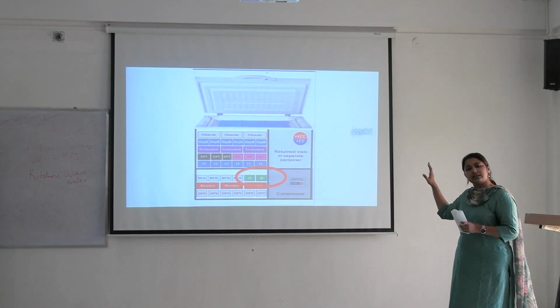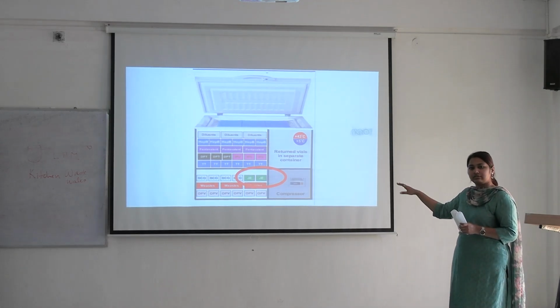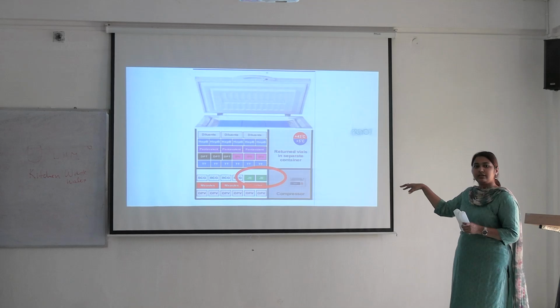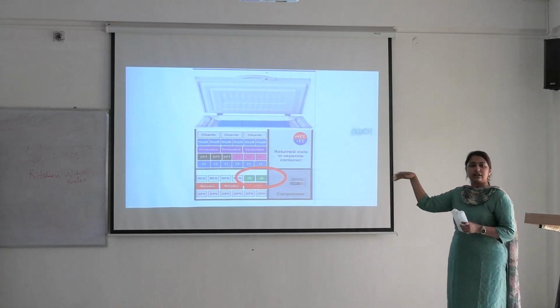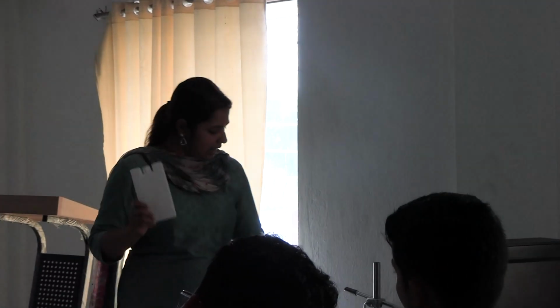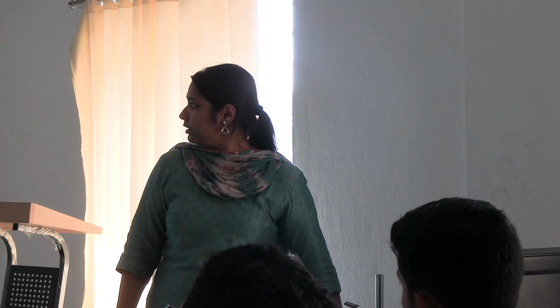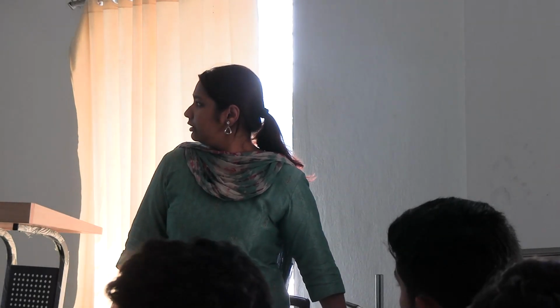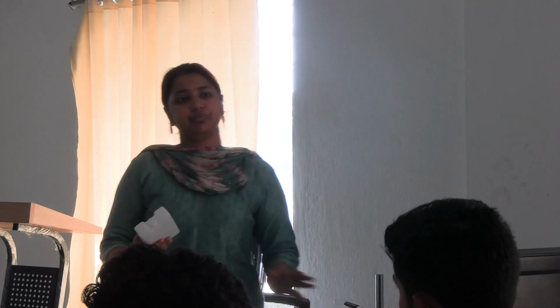The live vaccines are heat sensitive and killed vaccines are freeze sensitive, usually, so they are kept separately accordingly, and within the baskets always. The deep freezer looks different, and the temperature there is -15 to -25. And then again, the other two non-electrical appliances we covered, the cold box and the vaccine carrier.